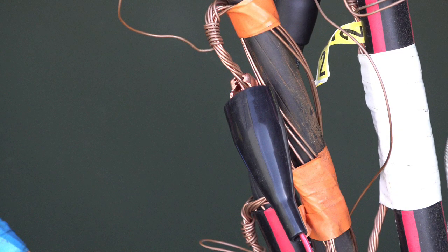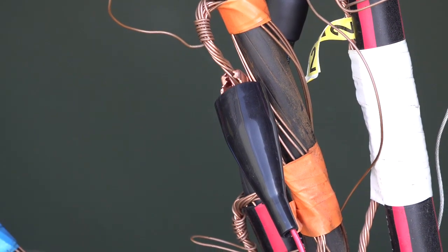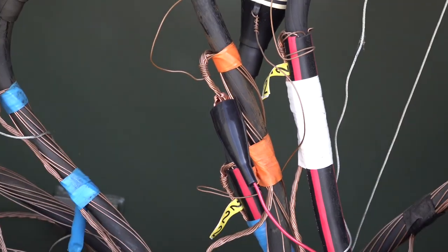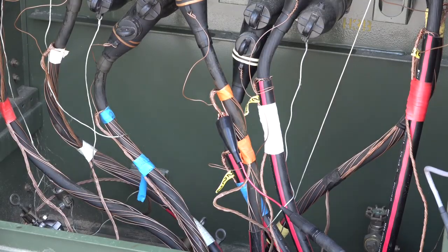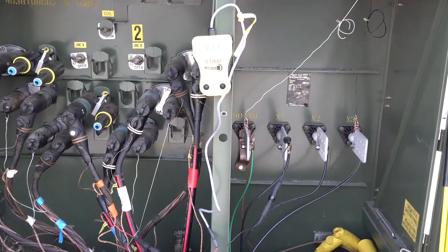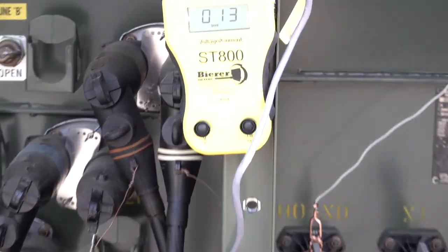Again, it does not matter which lead you attach to the hot secondary power or the concentric, but be aware of which one it is so you can identify it in the field in the manhole or the ditch. As you can see from our demonstration, by attaching the red lead to the concentric, we will now be looking for the arrow pointing away from the ST800 in the manhole or the ditch. Once we've made our proper connections, go ahead and turn on the ST800 and take note of the voltage. Make sure that we have 120 volts and the unit is operating properly.